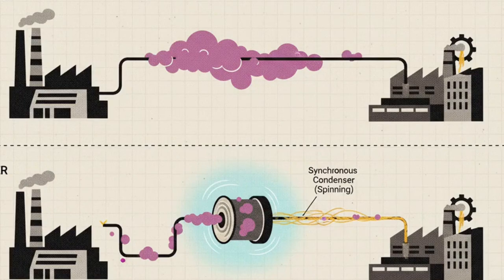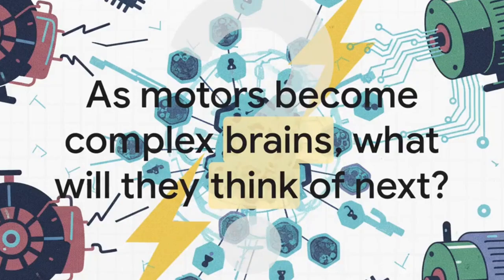So you just stick one of these useless motors in a factory or a substation. It just spins, it floats on the grid, and by fine-tuning its excitement level, you can have it supply all the reactive power needed right there on site. This frees up the entire grid, it cuts down on waste, and makes the whole system way more stable and efficient. A motor that does nothing is actually doing everything. So we've gone from these simple workhorses to precision machines, and finally to these intelligent devices that can stabilize the entire grid. The motor isn't just muscle anymore. With modern electronics, it's really becoming a brain. And as we rely more and more on electricity for everything, you just have to wonder, what problem will this incredible machine solve for us next?